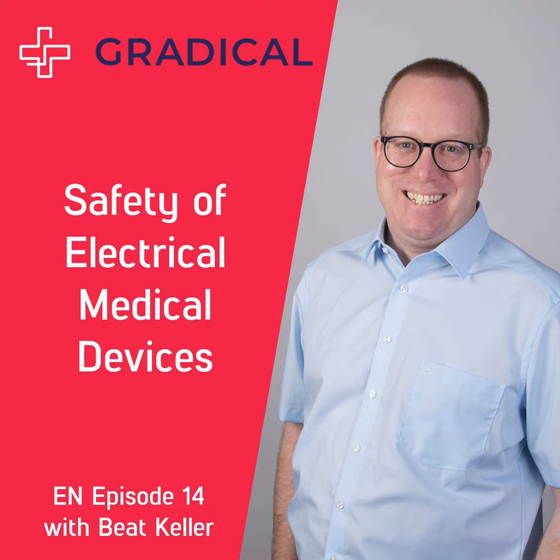The insulation of wires and connectors in there need to have then V2. What I often see is that, especially for connectors, there are connectors which have V1 or V2, but only as a self-declaration of the manufacturer. The one which has a certification from a third party then directly is a V0. That is one reason I often see V0 connectors and insulation used, because the ones which are certified are usually then the V0 connectors.